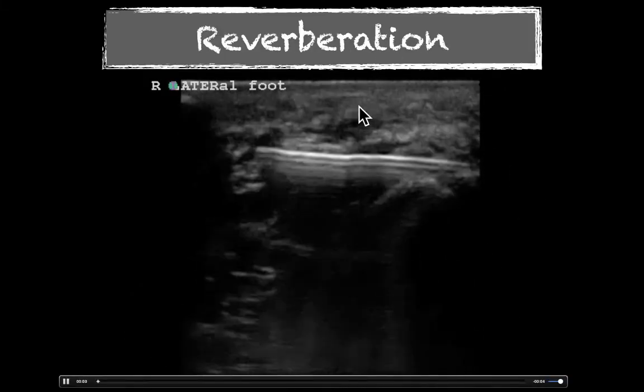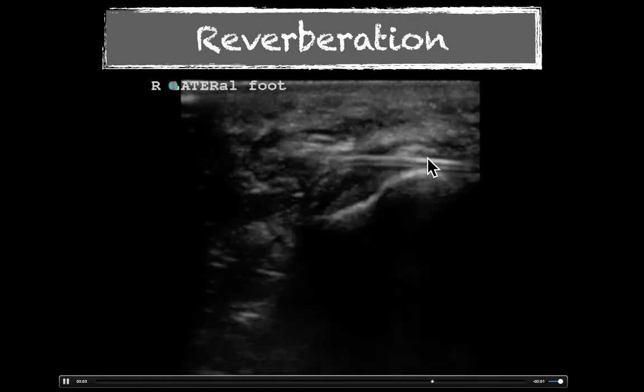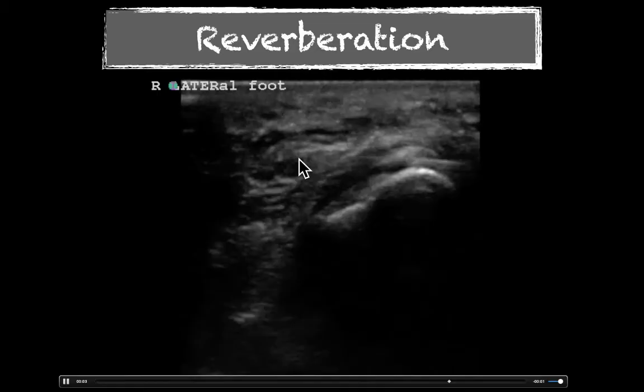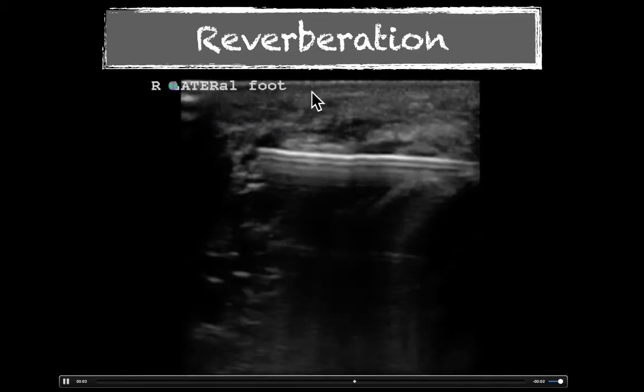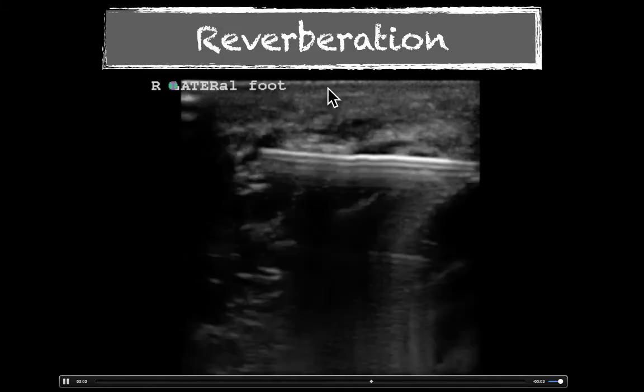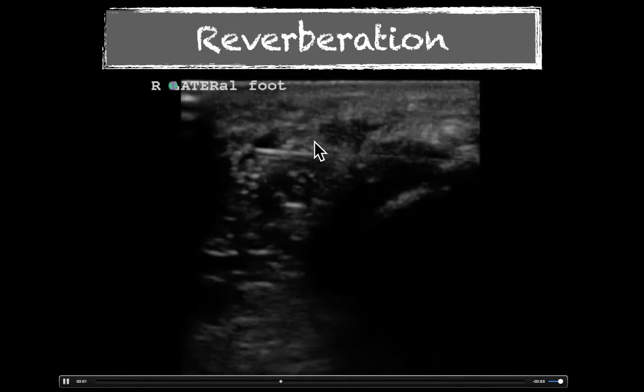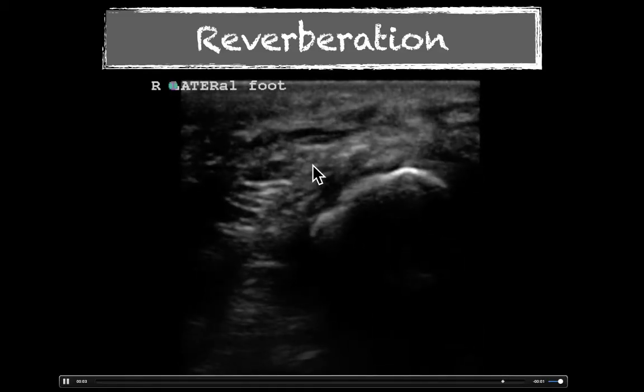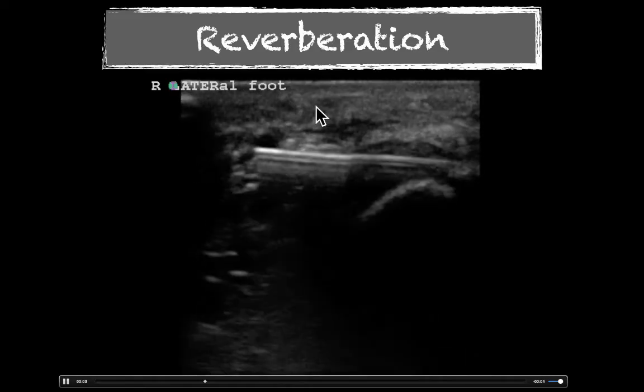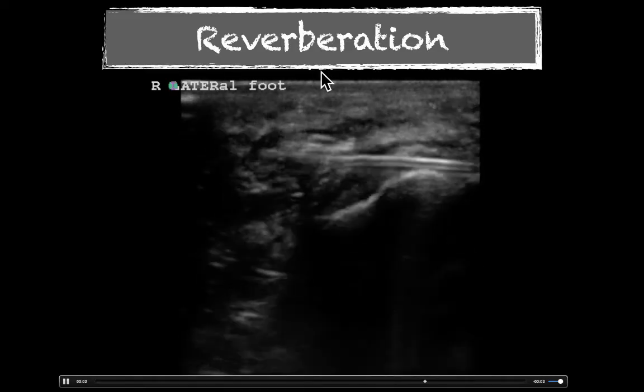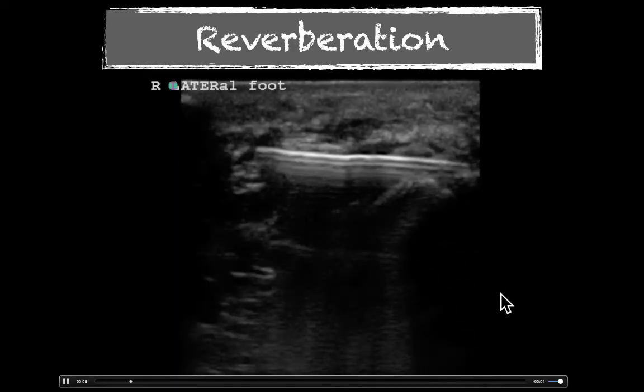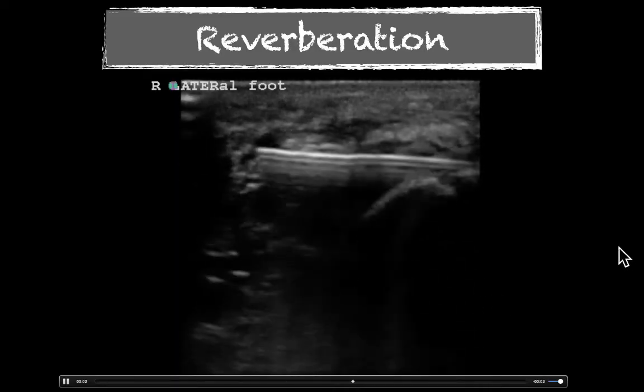We have reverberation artifact. What happens is you have a structure — this will often be seen in foreign bodies or during needle placement. An ultrasound beam travels down, some of it hits the needle and brings it right back up to the probe so you see the structure, but some of it makes it past the needle, comes back, hits the needle, bounces back, hits the tissue, and makes it back up to the machine. It kind of ping-pongs back and forth and creates what looks like additional structures down below, as you see coming off the needle.